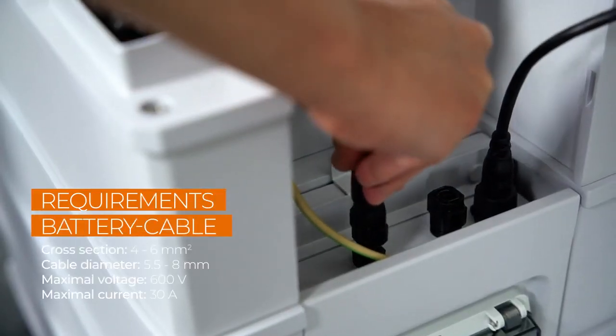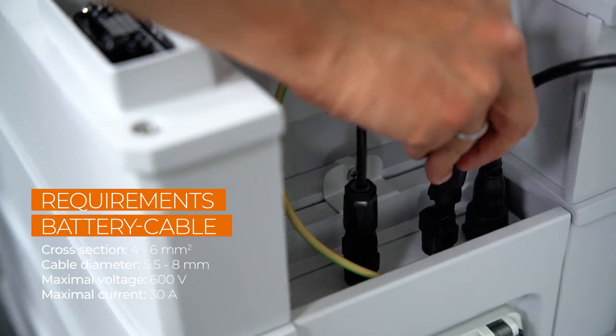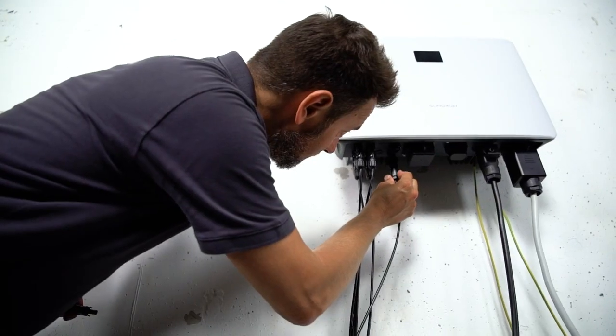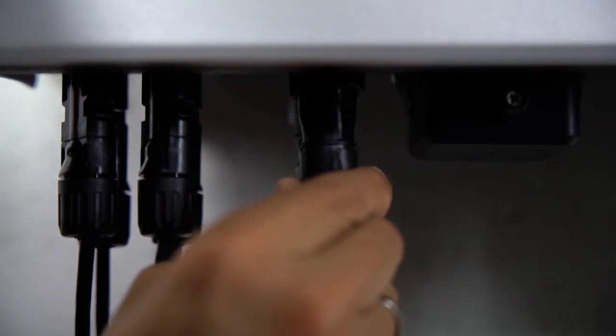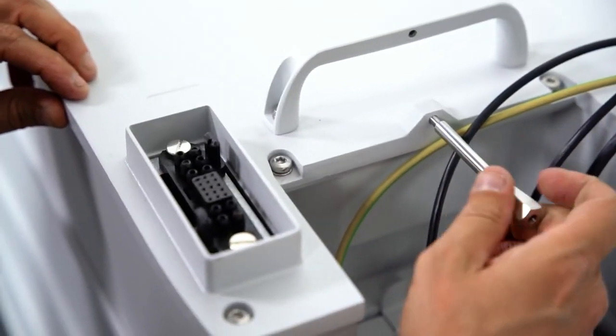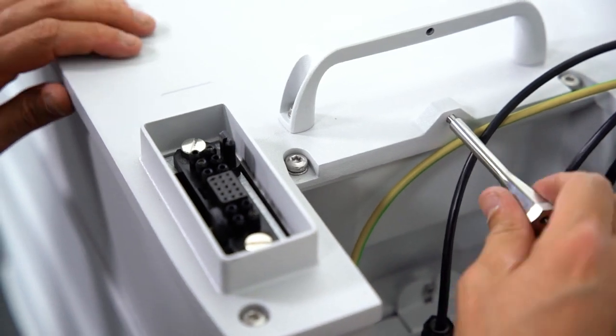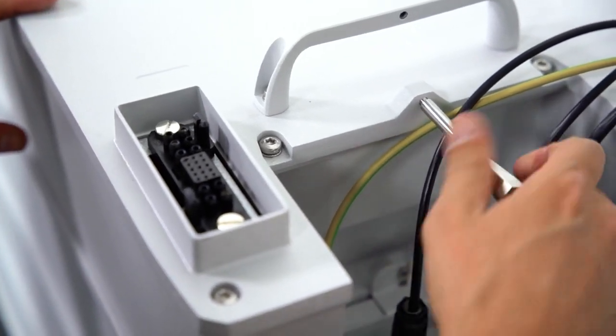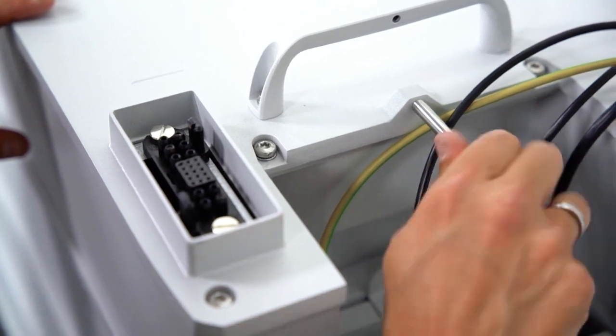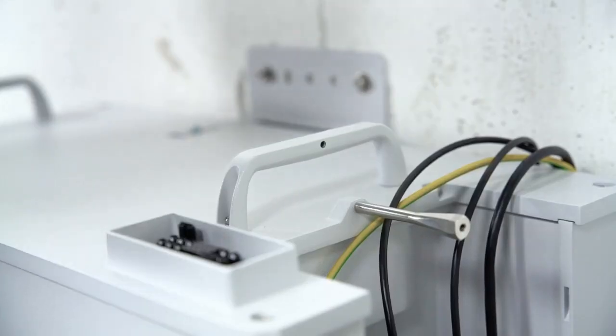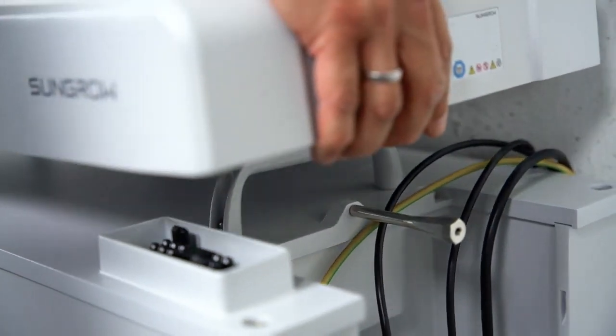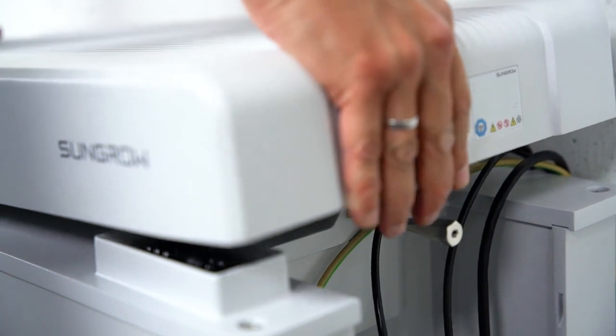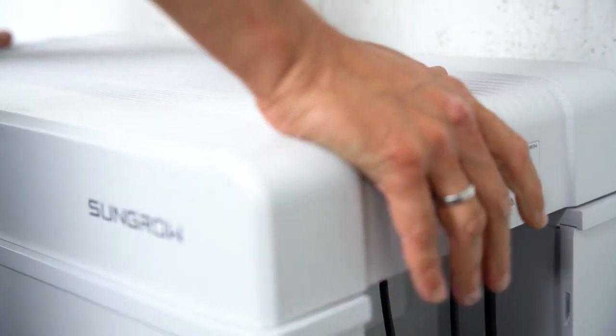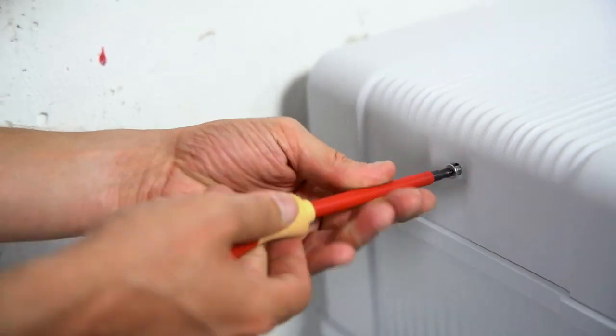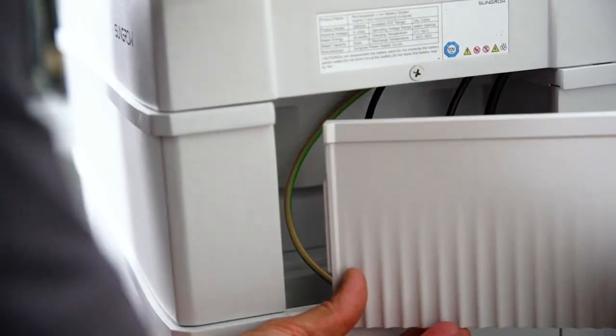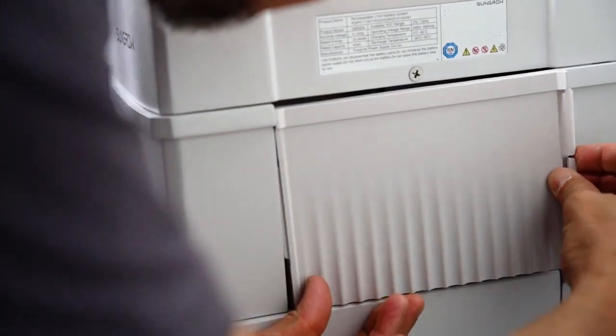Connect the power cables to the P- and P+ port on the battery side. The cables also need to be connected on the inverter side. Fix the switchgear with the stud, which is part of the delivery scope. Due to continuous product updates, the fixing may work a little different. Check the user manual for the latest instructions. Make sure that all cables are correctly positioned to fit into the intended recess in the cover of the battery. Place the cover on the battery and fix it on both sides with the included M5 screw. Clip in the side cover. That's it. Quick and easy.